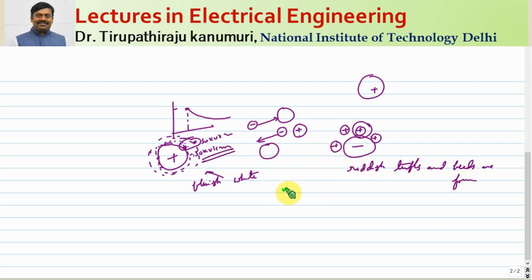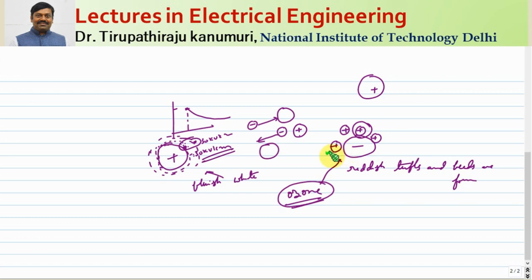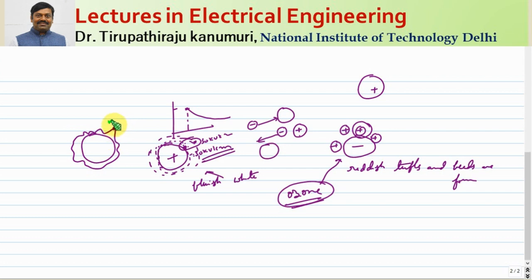Along with the light, ozone gas is also produced. This ozone gas can be detected by its smell, and its disadvantage is that it corrodes the conductor surface. It is also observed that the extent of breakdown depends on the shape of the conductor — circular shapes are less affected. In ACSR conductors, or when dust accumulates, the potential gradient is maximum at sharp points, where corona occurs first, even below 30 kV per centimeter.